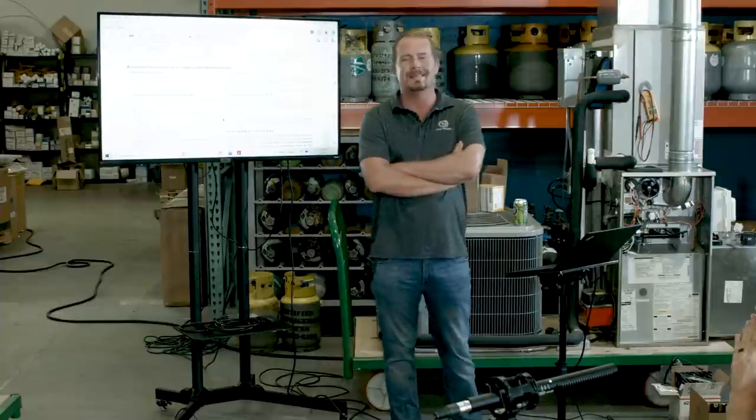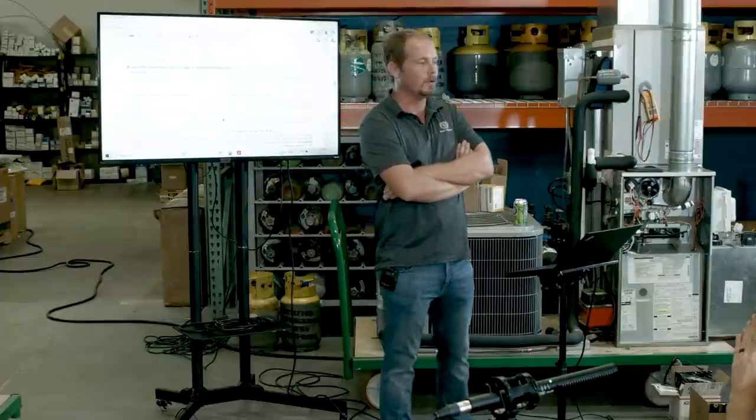And why would we need that on a heat pump, specifically on a Carrier system, in heating mode only? Why would it only matter in heating mode and not in cooling mode? Interesting, perplexing. Any thoughts? Yeah. What? No TXV in the condenser. Yes, Elijah, very good. No TXV in the condenser. So what does that mean? That means that while you have hard shutoff capability when the system is running in cooling mode, in heating mode, you don't have that. So where's your condenser in heating mode?